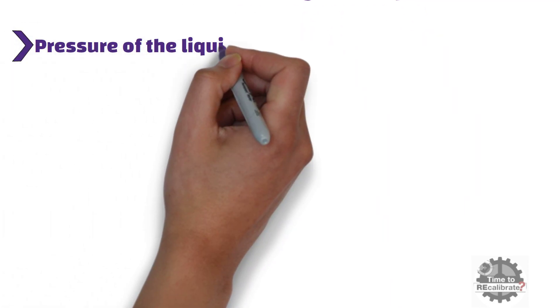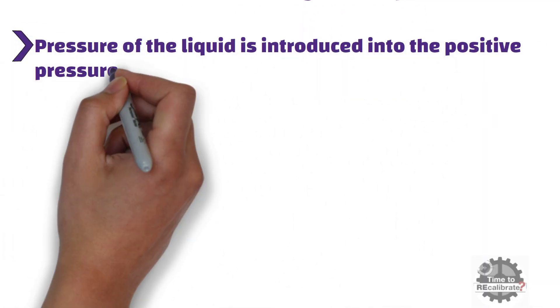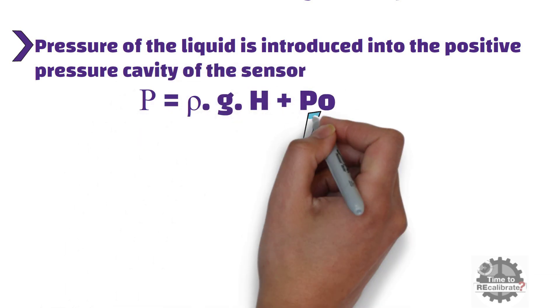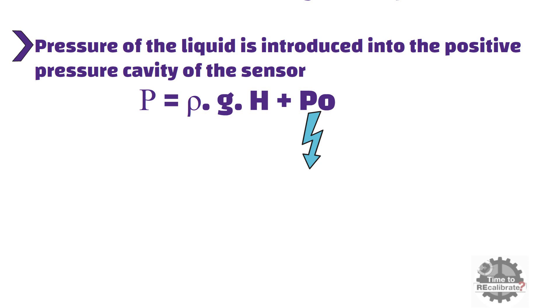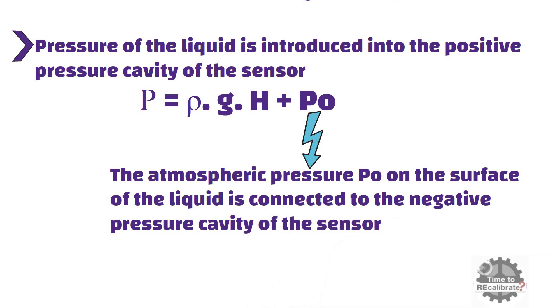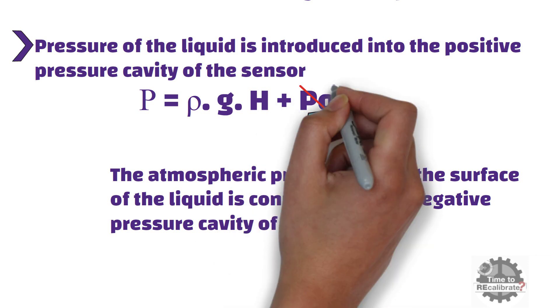Here, the pressure of the liquid is introduced into the positive pressure cavity of the sensor through the gas-conductive stainless steel. And the atmospheric pressure P0 on the surface of the liquid is connected to the negative pressure cavity of the sensor to compensate the P0 at the back of the sensor.